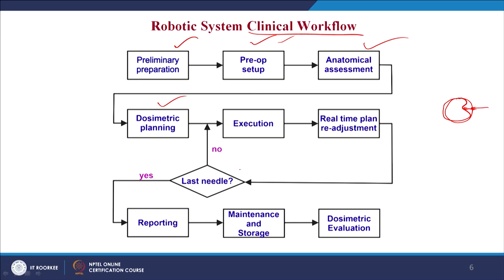This process is repeated for all needles. If it is not the last needle, the system goes back to execution and real-time readjustment. Once the last needle is done, the reporting part comes into picture, where a report is prepared as per the American Association of Physicists in Medicine Task Group and produced for final approval. This report is maintained and stored for the dosimetric final evaluation. This completes the overall clinical workflow of robot assisted prostate brachytherapy minimal invasive surgical procedure.